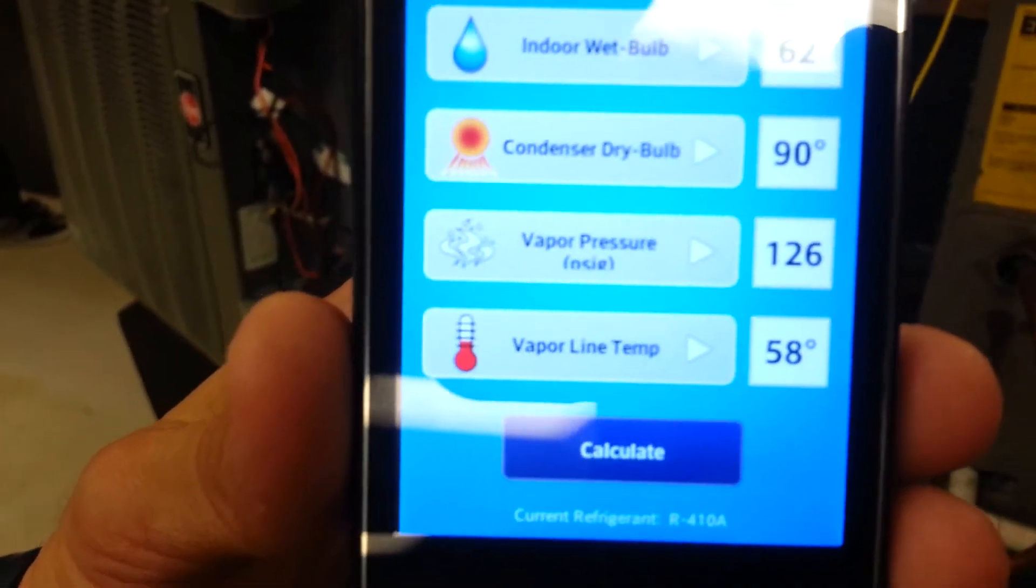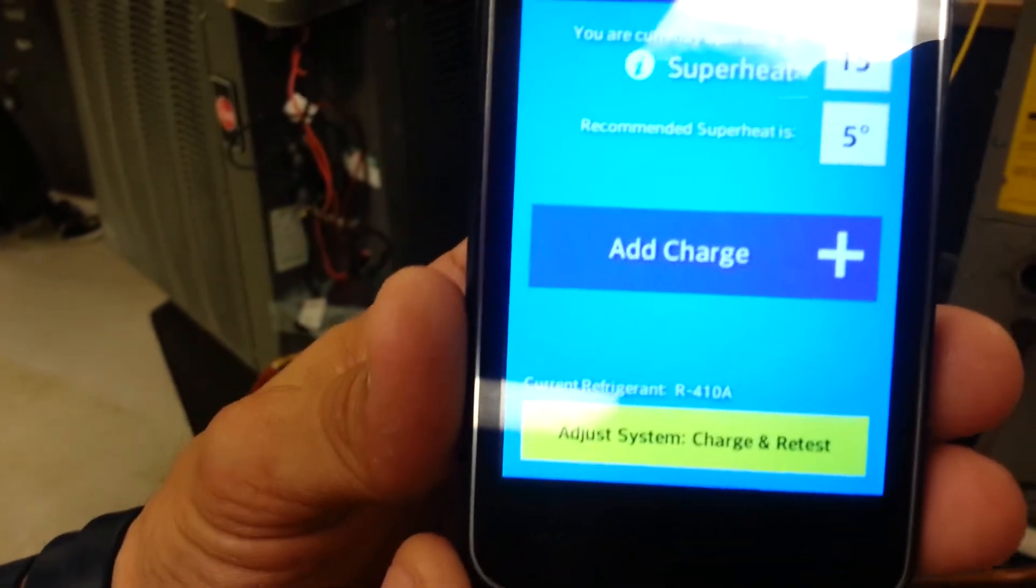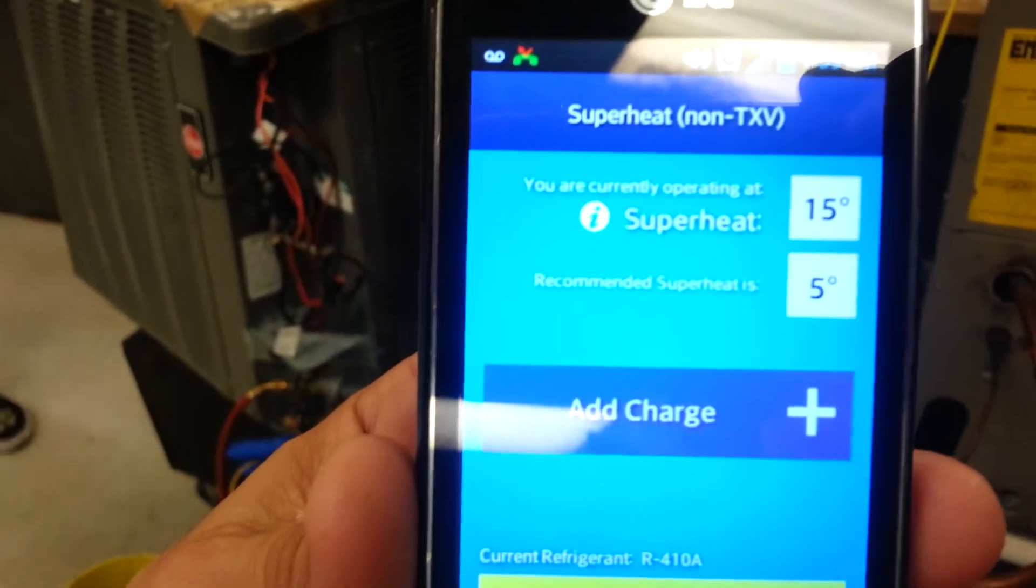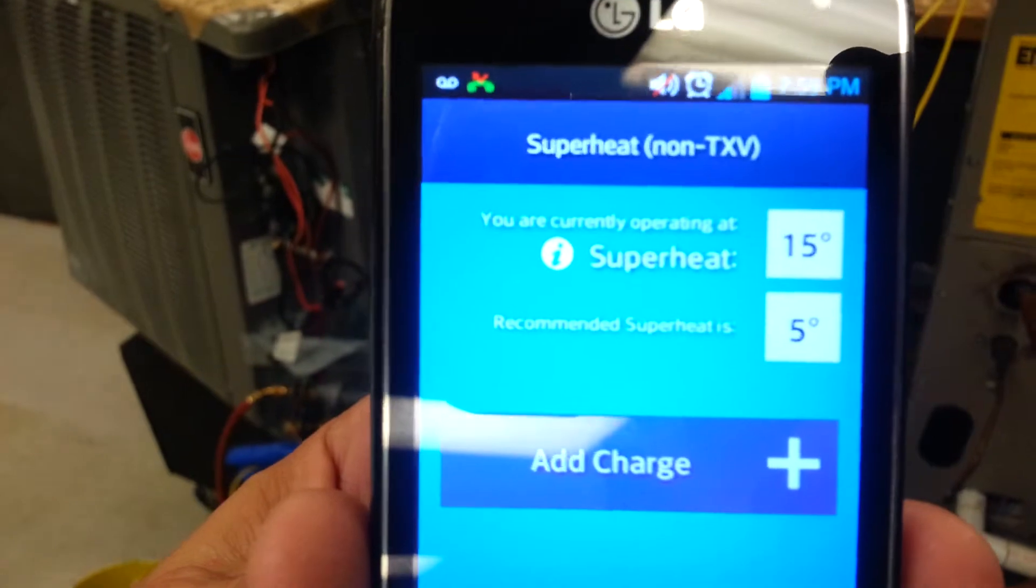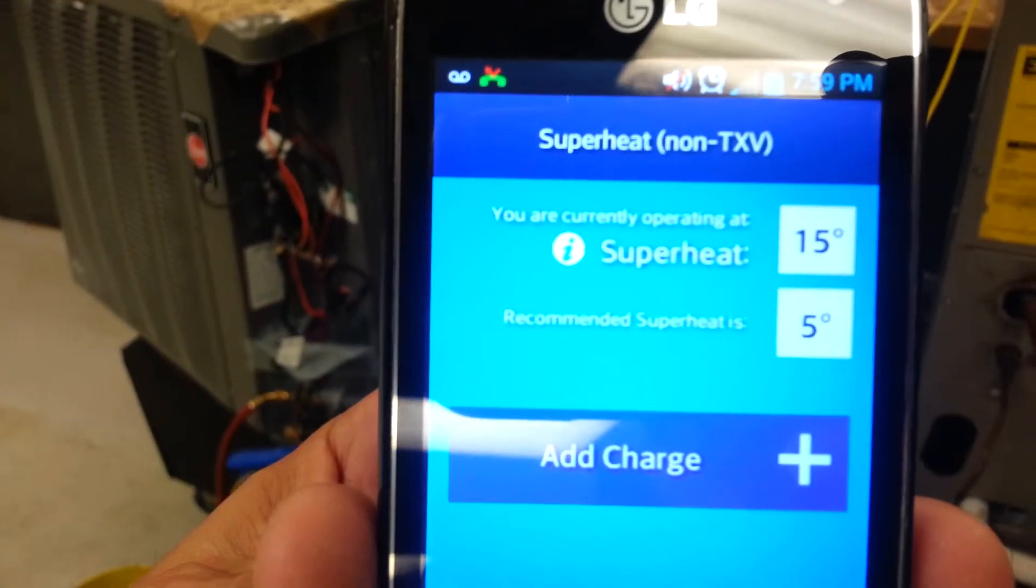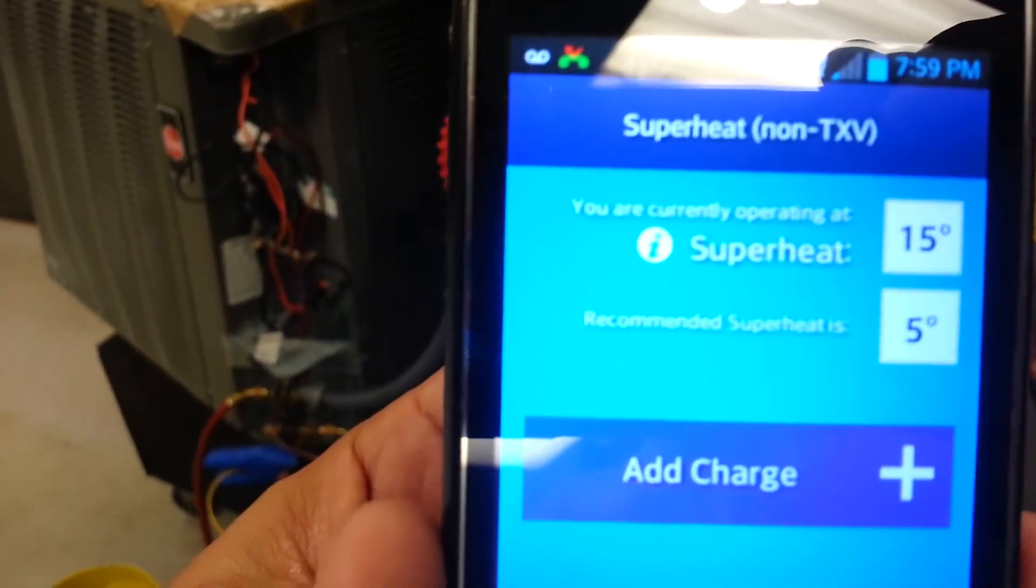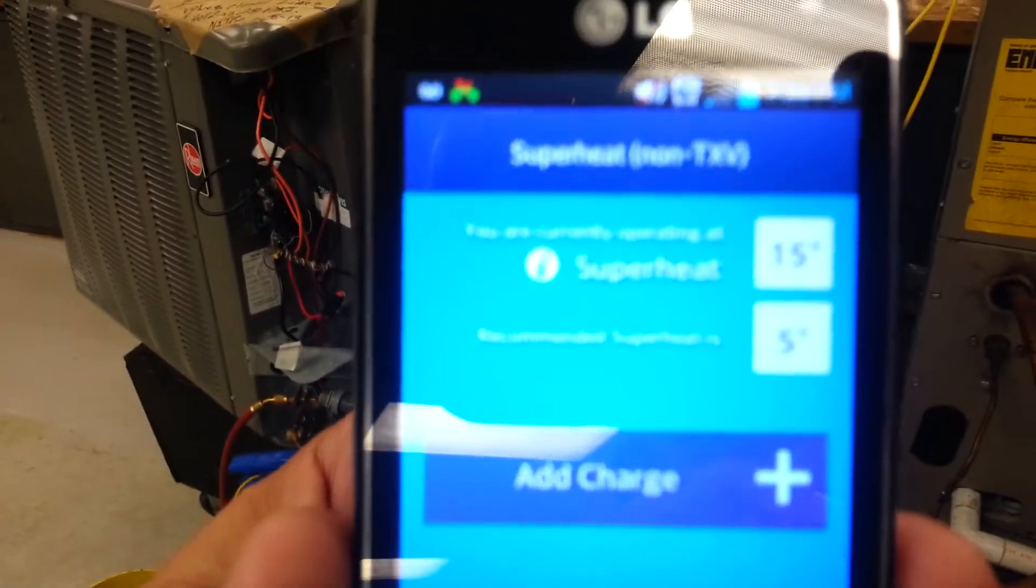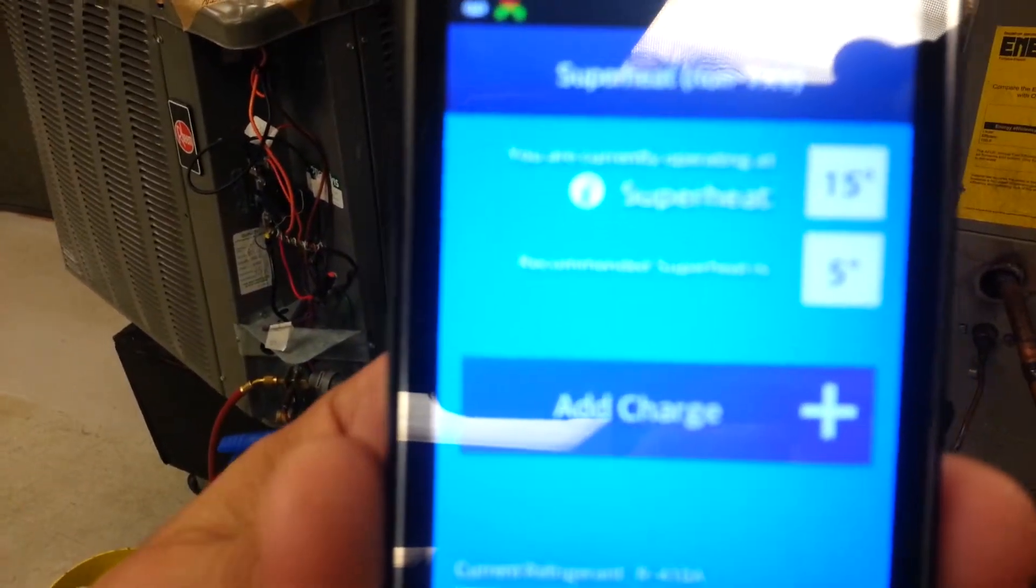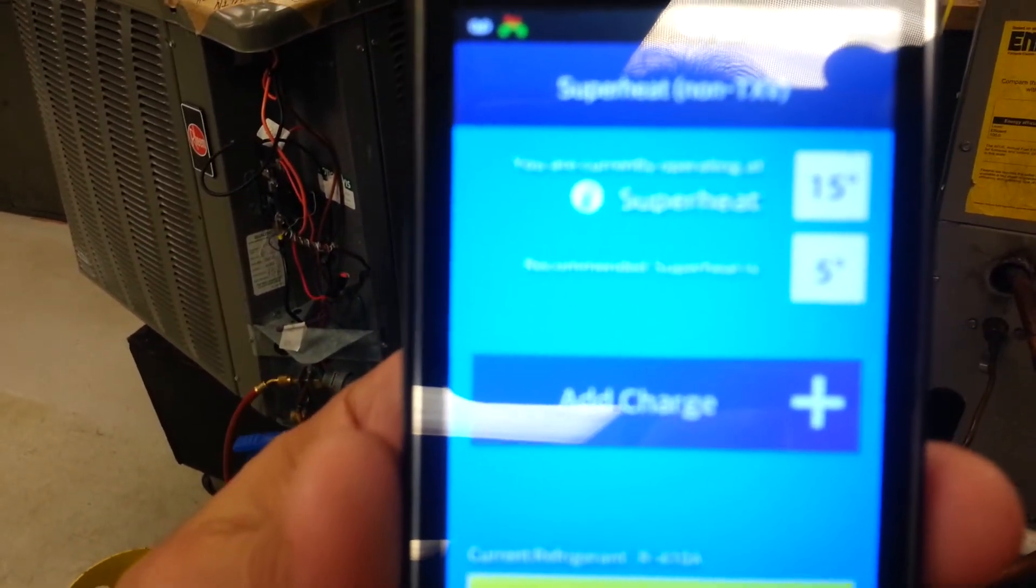Then you calculate. It's calculating, then it's saying add charge. Okay, our actual superheat is 15 degrees Fahrenheit, but our recommended superheat is 5 degrees Fahrenheit. So what we're going to do is add charge to it, and then we're going to come back and calculate it again.